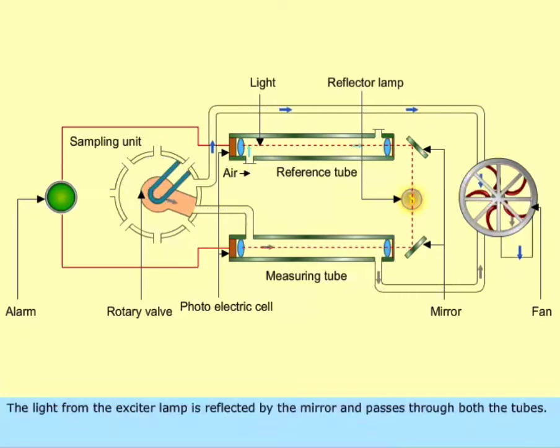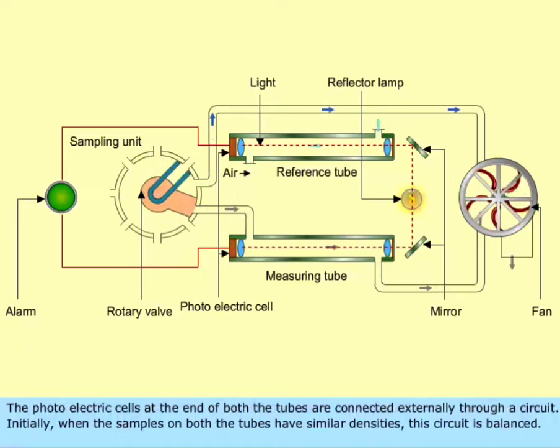The light from the exciter lamp is reflected by the mirror and passes through both the tubes. The photoelectric cells at the end of both the tubes are connected externally through a circuit. Initially, when the samples on both the tubes have similar densities, this circuit is balanced.